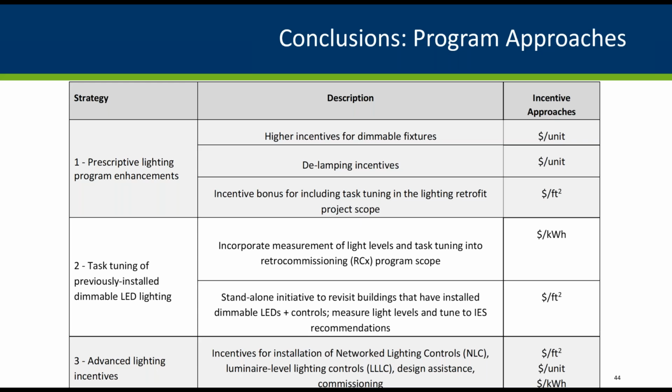In Minnesota, Xcel Energy offers incentives for network lighting control systems that are listed on the Design Lights Consortium Qualified Products list, is capable of high-end trim in addition to code-required daylight and occupancy controls, and has been properly commissioned. Many programs offer per kW or per kWh incentives based on custom calculations, although programs administered by Focus on Energy and AEP Ohio offer network lighting control incentives on a per square foot basis.